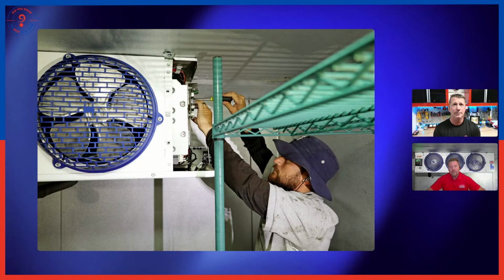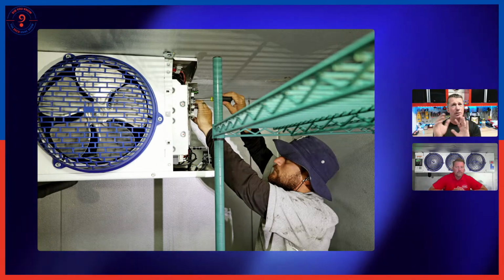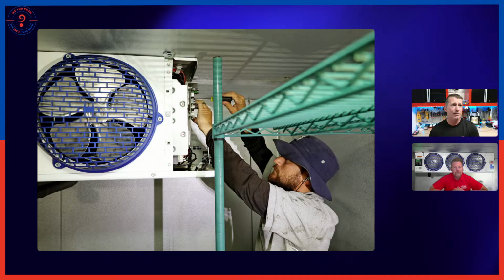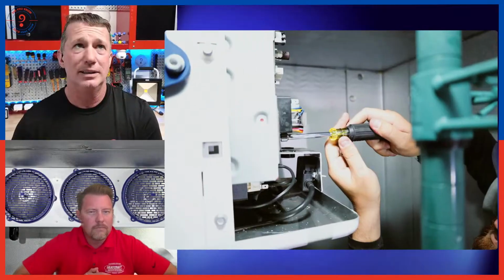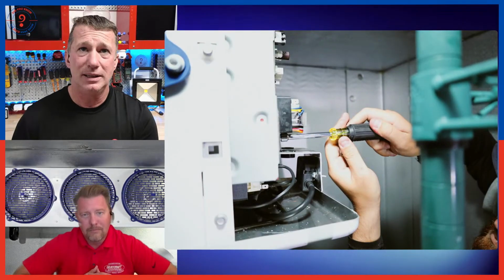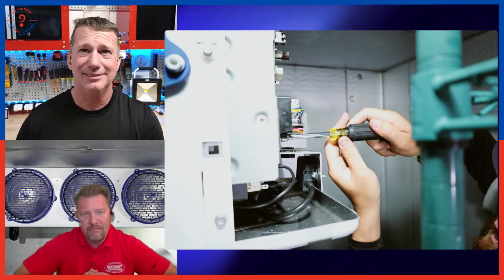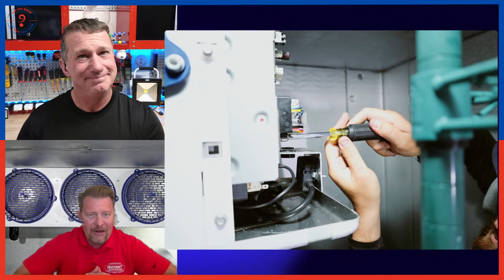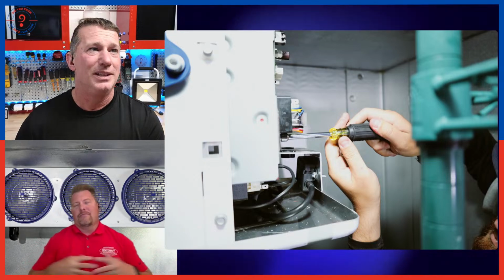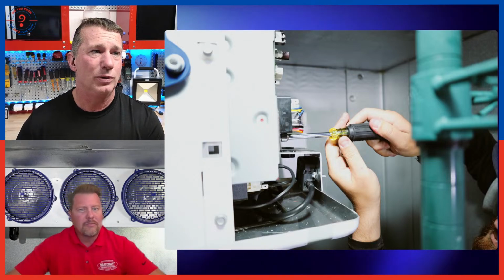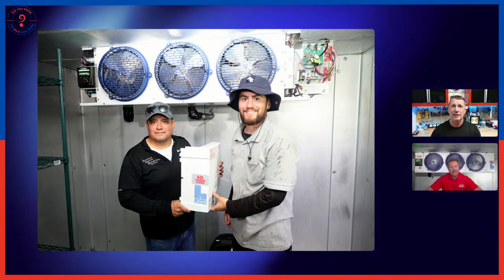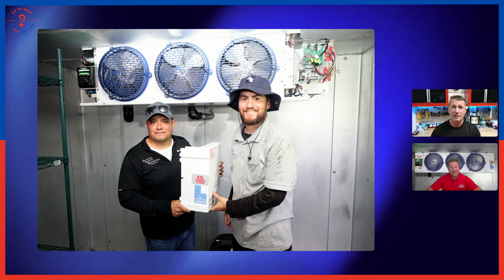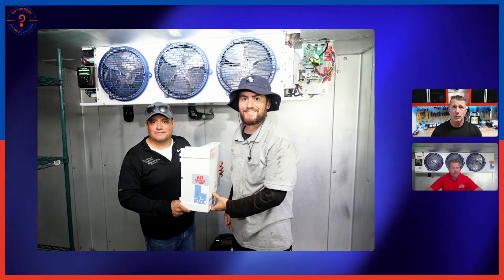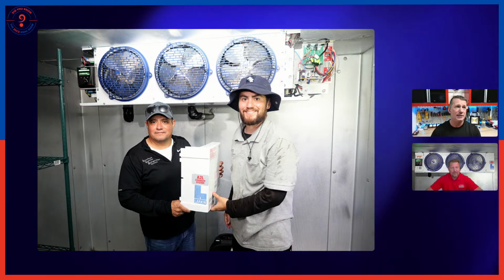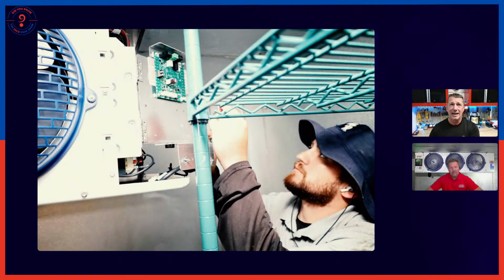So this particular one, facing the coil on the right hand side, once we remove the cover, we're going to see some things that may be a little different than what we've encountered in the past, right? You're going to notice immediately on this one, you can see your refrigerant detector sitting down there on the bottom right. Exactly. And to be able to get access to that, once we remove that right panel, there's that A2L sticker. If it was an A1 system, we wouldn't need the A2L sticker, but with an A2L application, we can put the A2L sticker on it. And then we're going to be able to gain access to that electrical control.